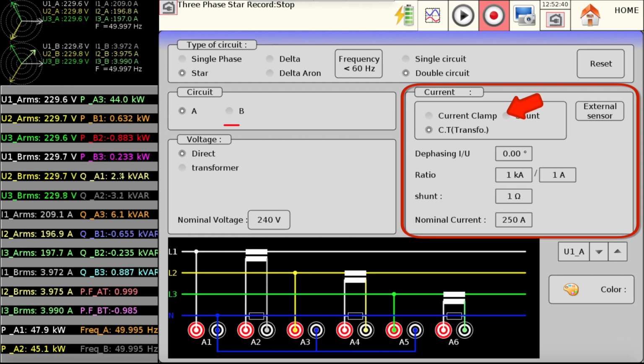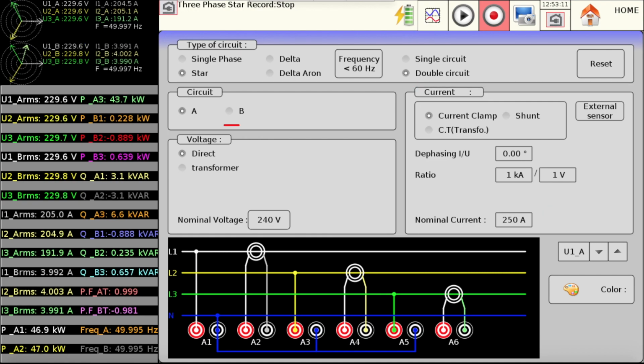Let's select a clamp. Our current clamp measures 1 kA for 1 volt. Now that the clamp is configured, we need to set our nominal current. The nominal current of our installation is 200 amps, so we select 250 amps to have a little margin.